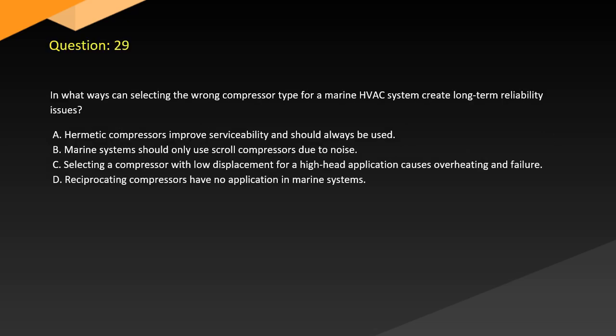Question 29. In what ways can selecting the wrong compressor type for a marine HVAC system create long-term reliability issues? A. Hermetic compressors improve serviceability and should always be used. B. Marine systems should only use scroll compressors due to noise. C. Selecting a compressor with low displacement for a high head application causes overheating and failure. D. Reciprocating compressors have no application in marine systems.